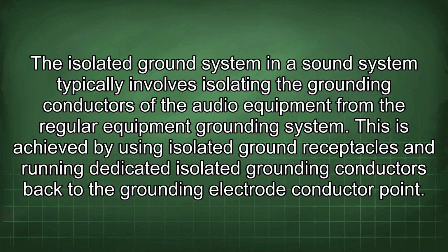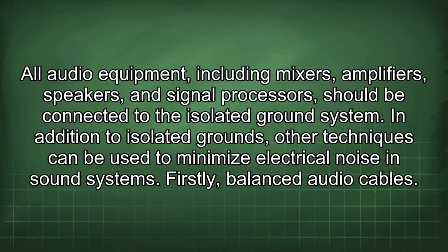This is achieved by using isolated ground receptacles and running dedicated isolated grounding conductors back to the grounding electrode conductor point. All audio equipment, including mixers, amplifiers, speakers, and signal processors, should be connected to the isolated ground system.